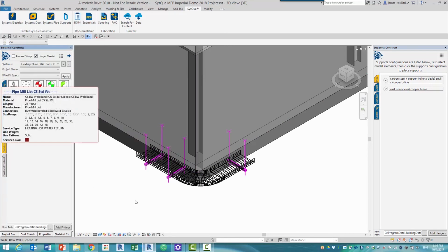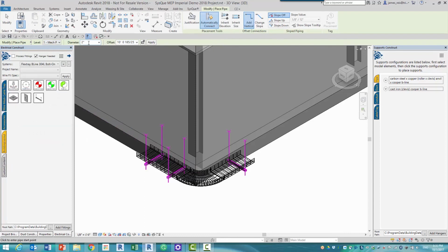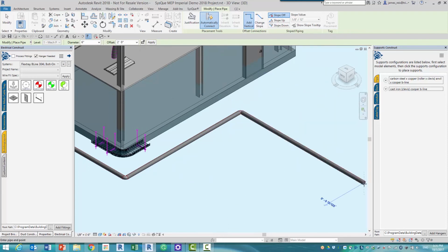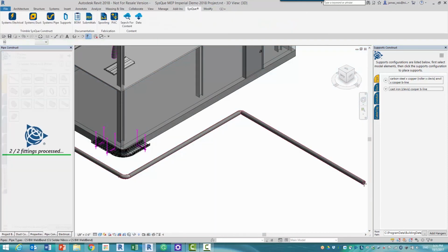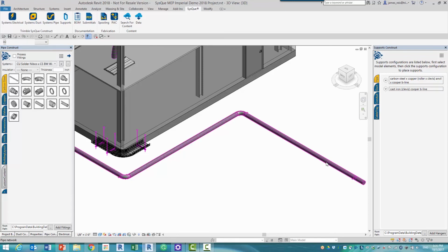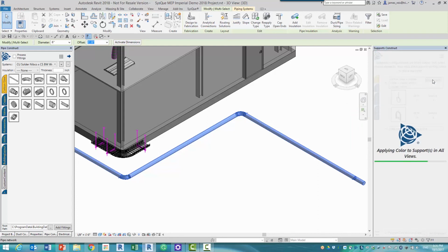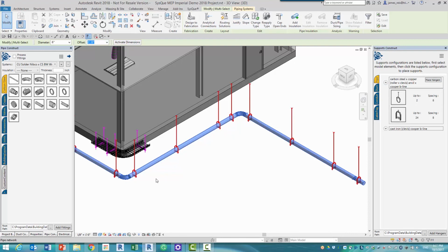So for example, if I take some pipe here and I route this pipe 6-inch, I'll keep it the same relevant elevation we had earlier. Select the pipe run. You can go to pipe. You can see what type of hangers will be applied, again with the size and the spacing. Place hangers. That's where the specification kicks in and automatically adds the hangers for us.